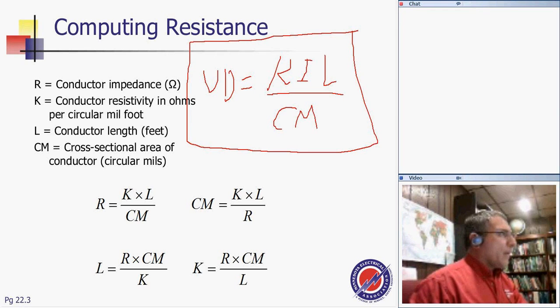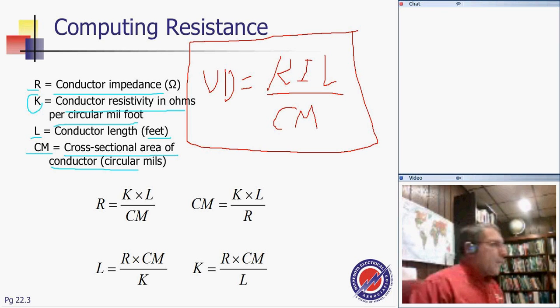And I'm sure a lot of you guys have seen this one. Here's what the K stands for. K is the resistivity in ohms per circular mil-foot, in feet, not meters. R, I don't have an R here, but R is the resistance of the cable, and CM is the cross-section area of the conductor. That finds the voltage drop. Suppose I don't care about the voltage drop. Suppose I want to find the conductor, right?